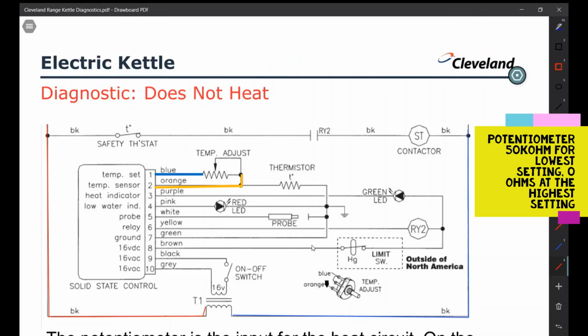All right, next we're going to set the potentiometer. It's 50k ohm for the lowest setting. 0 ohms would be the highest setting, so 10 would equal 0 ohms. So that would be an easy test. So we're coming off of these blue and orange wires right here. Okay, these can be jumpered out because we have 0 ohms at the highest setting.